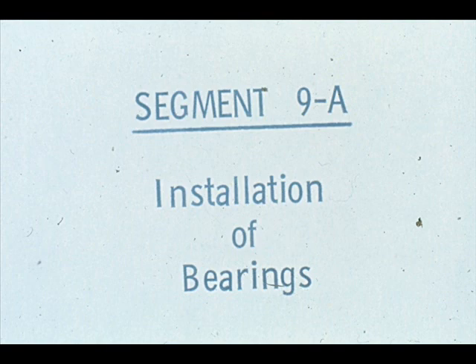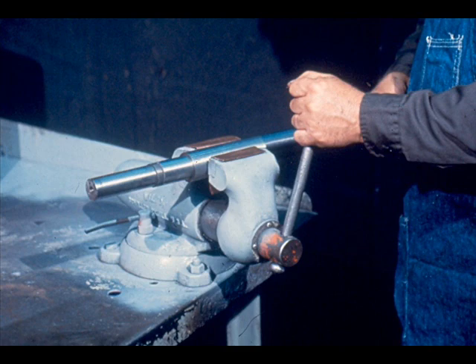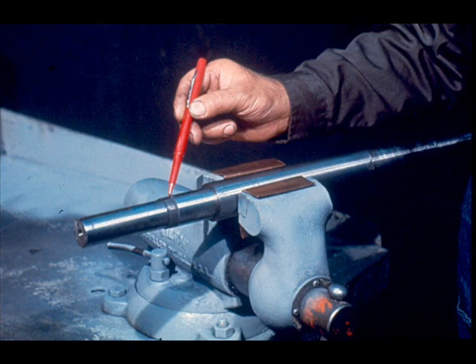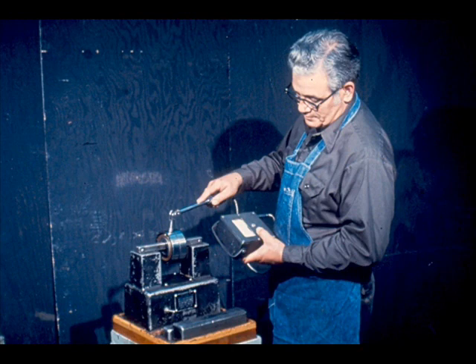This segment of our course deals with the installation of new bearings in the single-stage centrifugal pump we dismantled earlier. The bearing housing and shaft fits were carefully cleaned and measured and are ready for the installation of the new bearings. Our first step is to clamp the shaft in a vise equipped with protective jaws, in a horizontal position with the lock washer tab slot on top. To install the first two bearings — the angular contact bearings in a duplex mounting — you will need to heat them in a hot oil bath or induction heater.